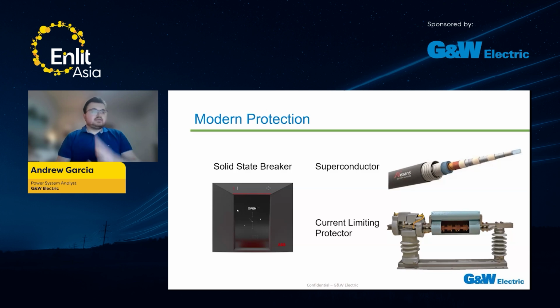Keeping moving around, we have a visual representation of these different types of technologies. On the left, you see the ABB solid state breaker. You can very much see how simple the interface is and the lack of mechanical parts that come with the device. They even have a nice power button in the upper right corner. You can also see a superconducting cable. It's a bit more complex than the traditional cables you would expect, and it's a very interesting kind of cable design. In the bottom right, you see G&W's current limiting protector, or CLiP. You can see inside the CLiP interrupter, the bus bar where the pyrotechnic charges are installed.